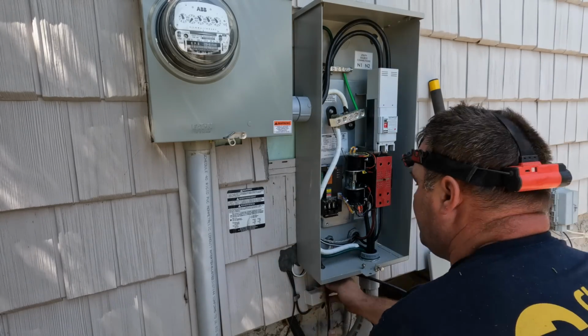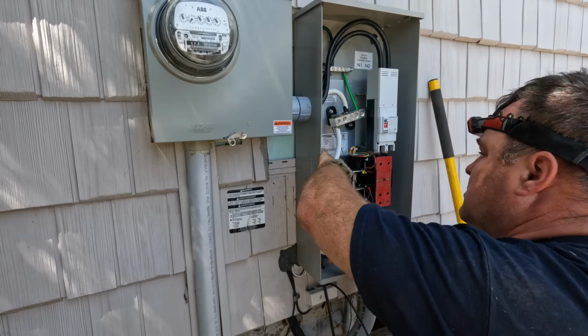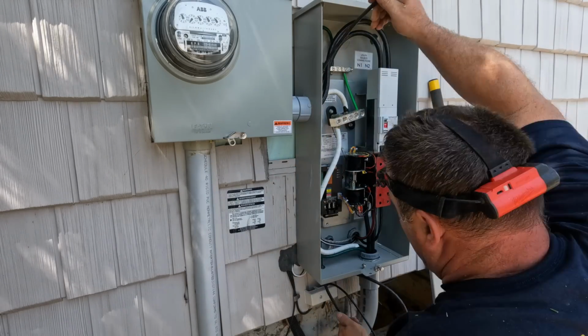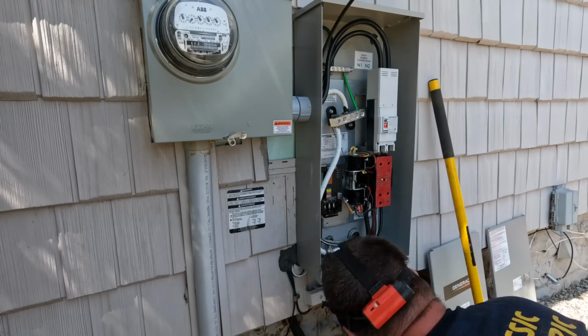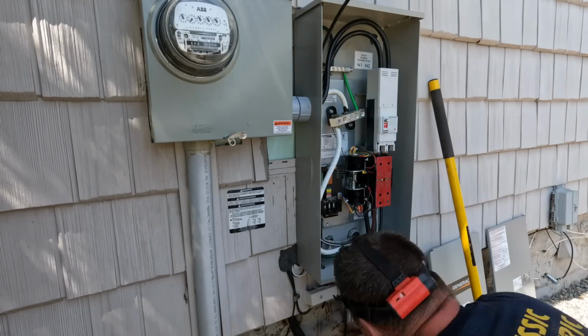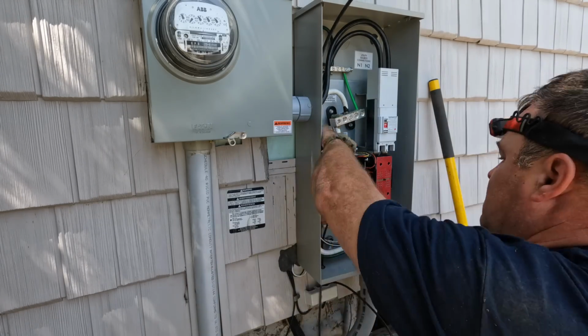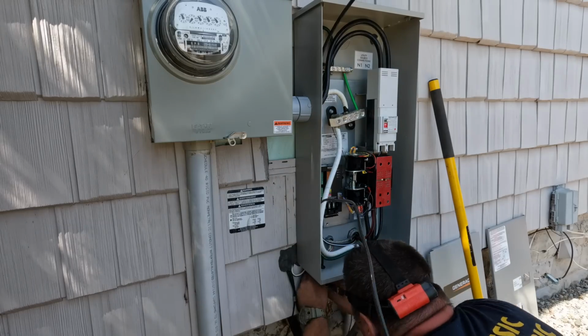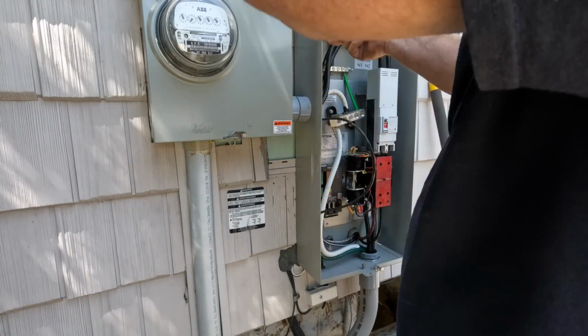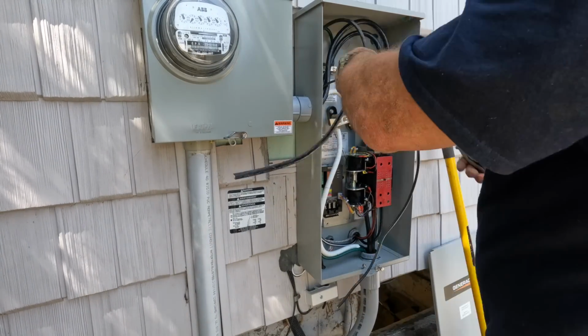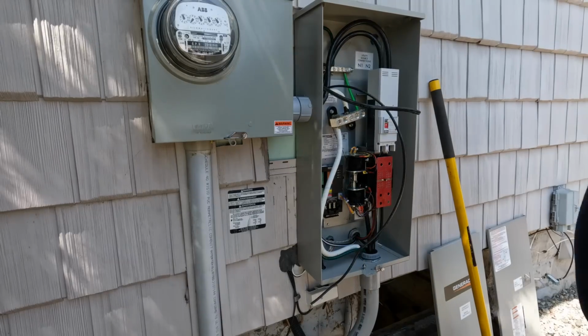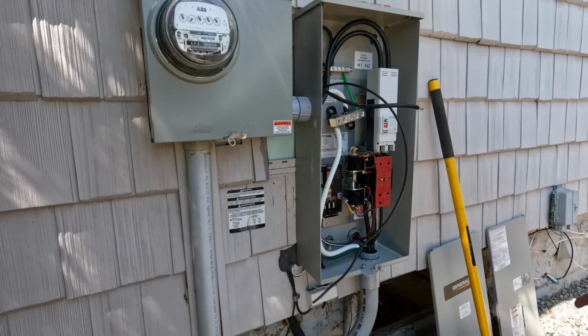The grounding electrode conductor that goes from the automatic transfer switch here, the main disconnect, to the copper water pipe in the basement is a number 2 aluminum. It attaches to the copper water pipe within the first 5 feet. And you'll see that later in the video, the wiring to the water main.